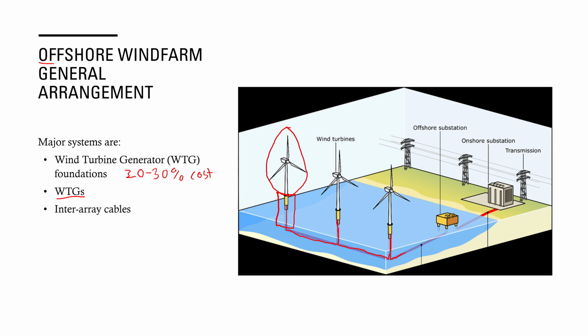You might have anywhere from 2 to 10 turbines on a string, and this cable gets thicker as you get closer to the substation because it's carrying more power from more turbines. On the last turbine on the string, this cable may be quite thin, or it may be made out of aluminium because it's cheaper and be the same size. So that inter-array cable takes the power from the wind turbines to your offshore substation.